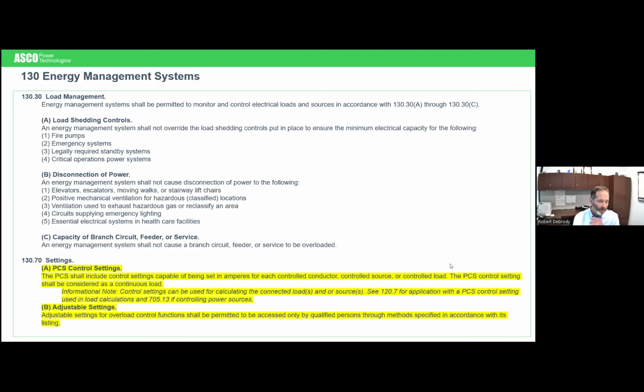Then 130.70, this is brand new stuff. It talks a little bit more about how a PCS system would work, controlling the amperages and making sure it's married up properly with the load as well as the sources—turning off generators if they're not needed, if the demand isn't there, and then turning them back on if the demand is there.